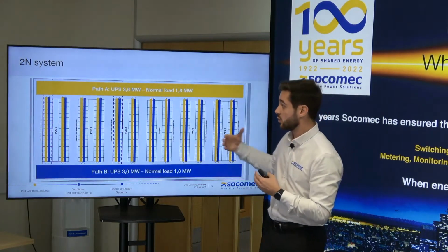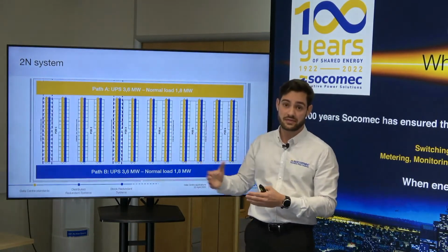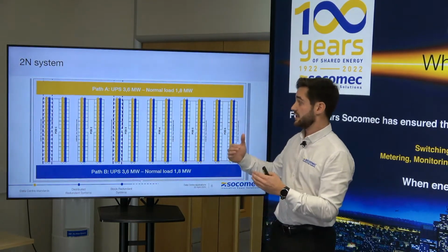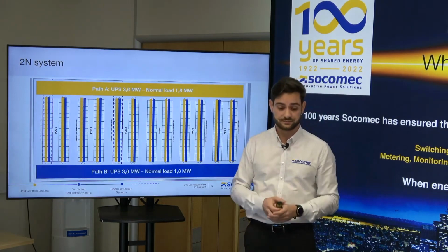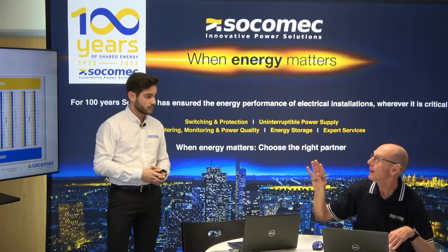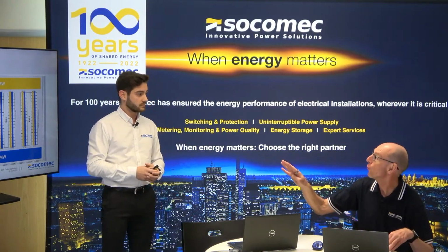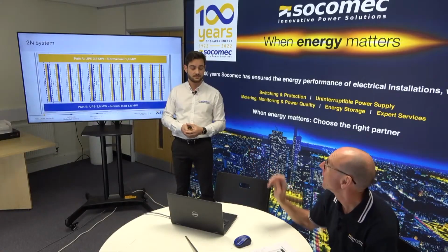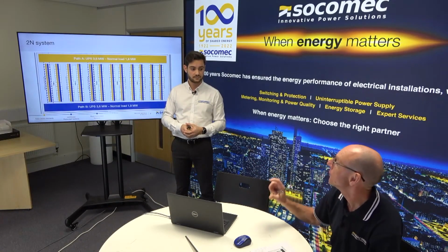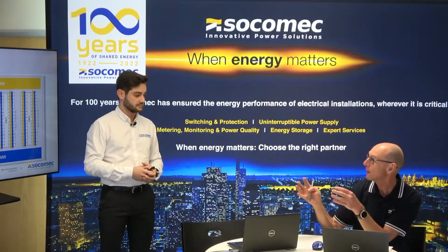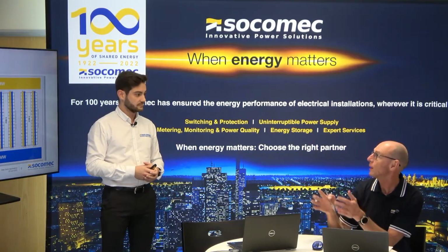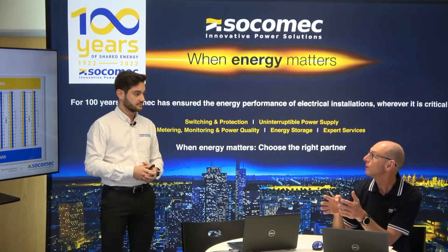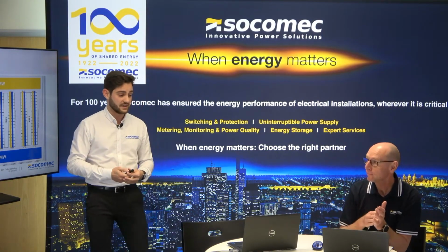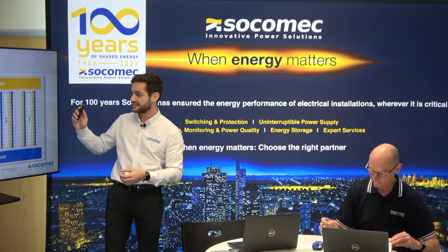If there is a failure on one path, then the secondary path can take the lead, kick off, and cover the overall load. So just to recap, that's in the Uptime Institute, a tier 4 data center we're looking at there. And obviously the redundancy, if you're looking at a monolithic UPS, it will be a complete monolithic UPS as a redundant path, whereas if it was a modular, it could be a module within the modular UPS. Absolutely correct. Yes, thank you for this clarification, Richard.